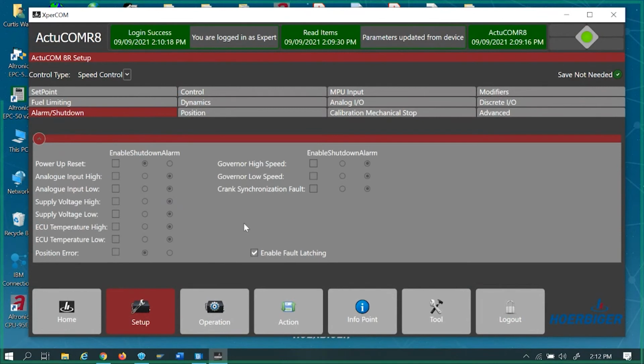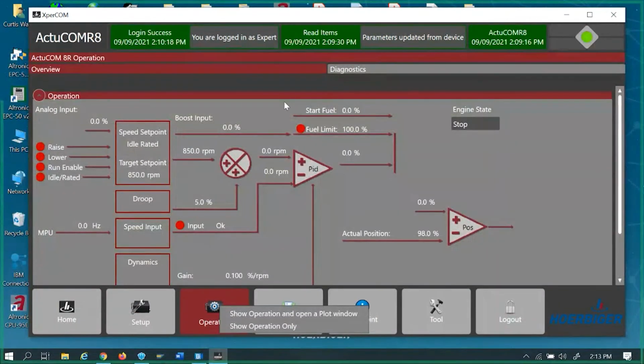Alarm shutdowns. I typically don't like to have any of my alarms on my governor. The only thing I would worry about as far as the governor is overspeeding or anything like that, or maybe missing gear teeth. If you get to know your operation page, you can almost troubleshoot just by watching this page do something if you need to.